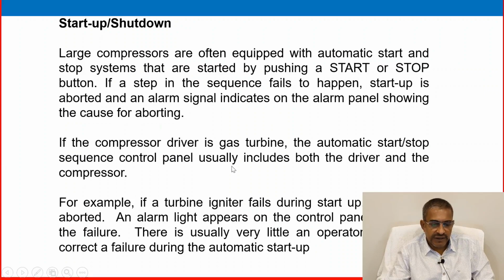If the compressor driver is a gas turbine, the automatic start-stop sequence control panel usually includes both the driver and compressor. For example, if a turbine igniter fails during startup, the startup is aborted and an alarm light appears on the control panel indicating the failure. There is usually very little an operator can do to correct a failure during automatic startup.